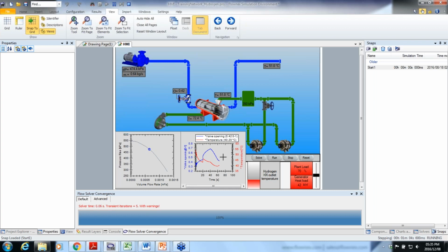Okay, so this is an example of how things can look in the end. As you can see there, this valve is controlling very nicely between a 30% and 70% opening, and the response is quick enough not to let the network run away. And obviously, this is where we would like to end off with any system.